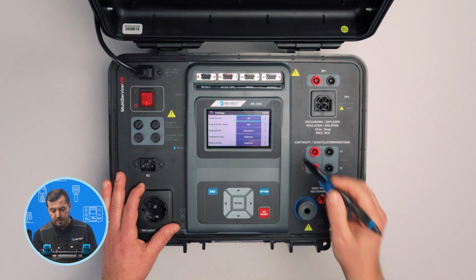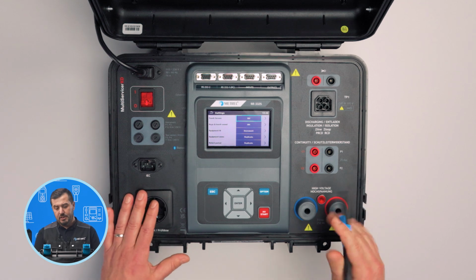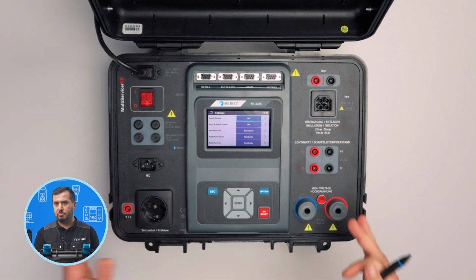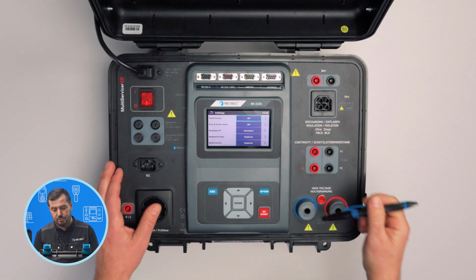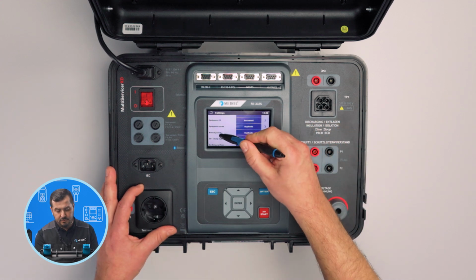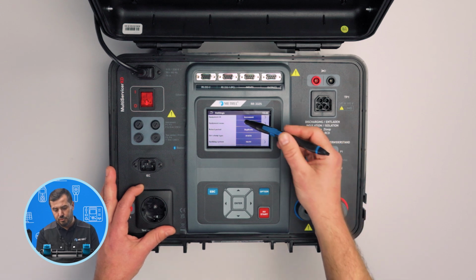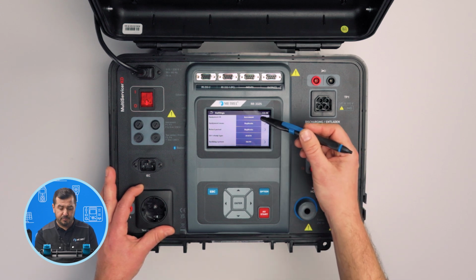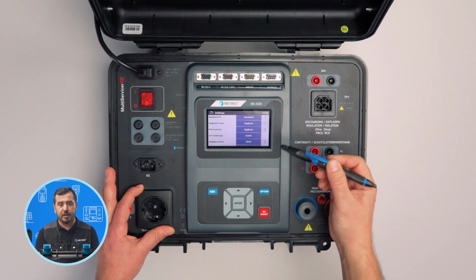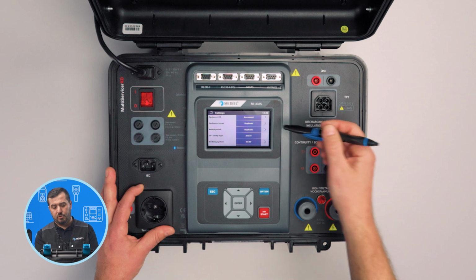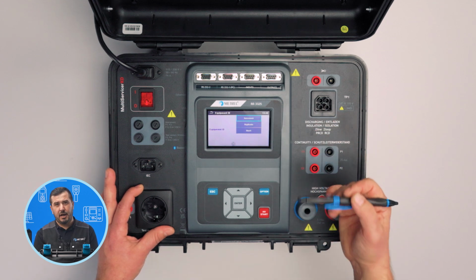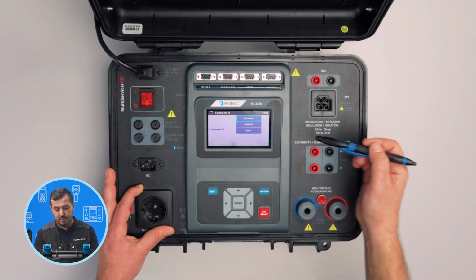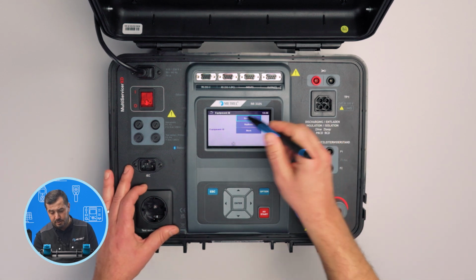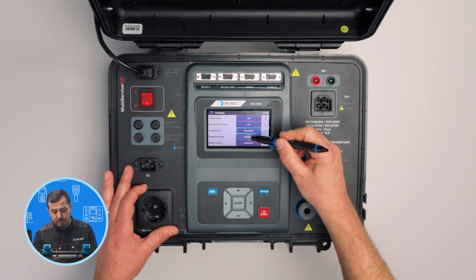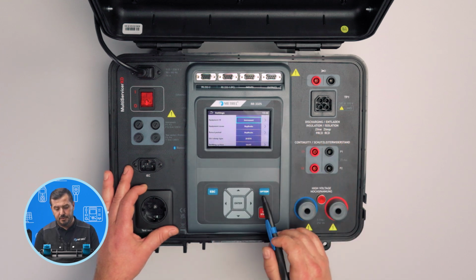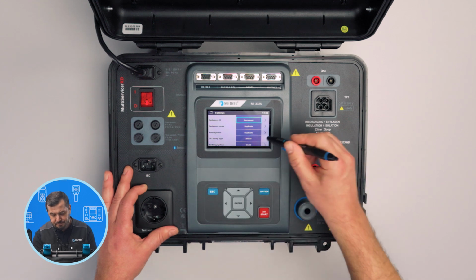Then a little bit larger submenu. This is the settings. Inside here we can, for example, adjust if we want to use the touch screen or not. Then we can also disable sounds. Then we have a couple of options which are dedicated to the parameters of special structure elements. For example, we can decide whether we want to increment the ID number, or we want to replicate it, or leave the field blank and each time enter it manually. The same option is available also for the equipment name and the retest period.